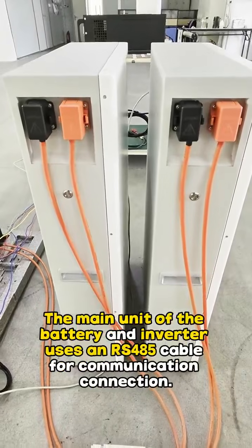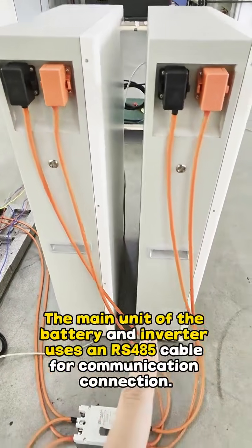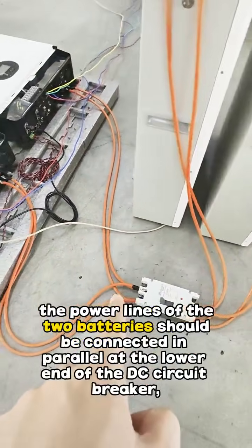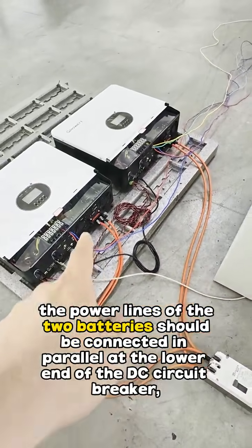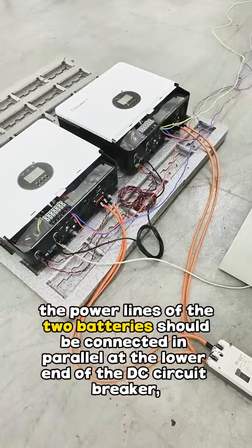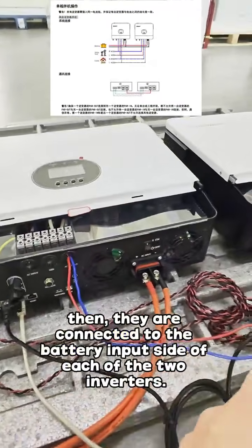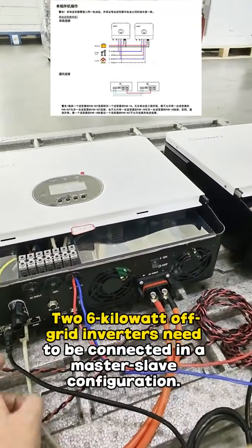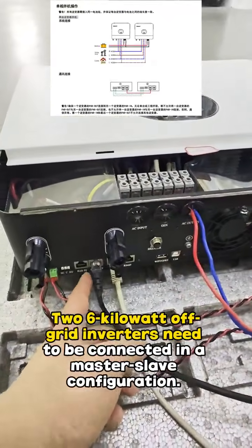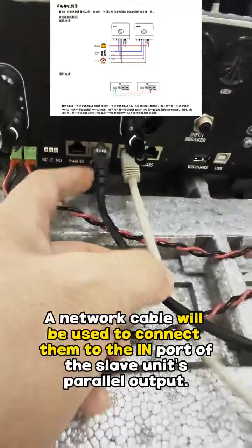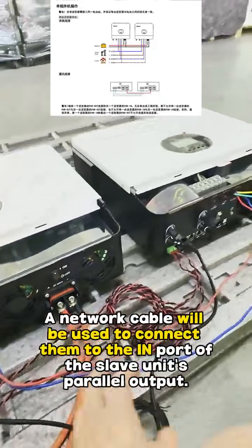The main unit of the battery and inverter uses an RS485 cable for communication connection. The power lines of the two batteries should be connected in parallel at the lower end of the DC circuit breaker. Then they are connected to the battery input side of each of the two inverters. Two 6 kW off-grid inverters need to be connected in a master-slave configuration. A network cable will be used to connect them to the in-port of the slave unit's parallel output.